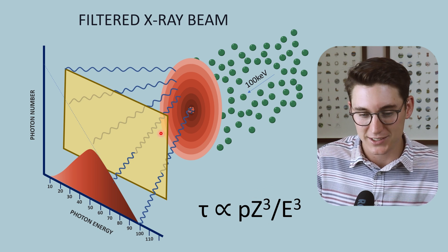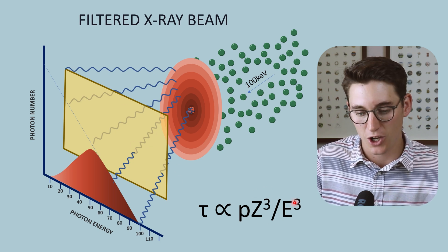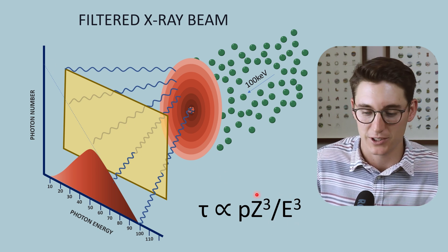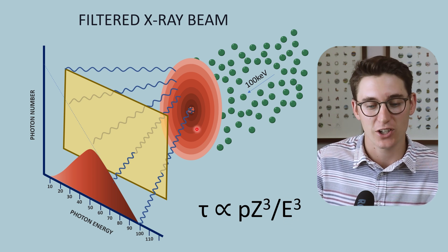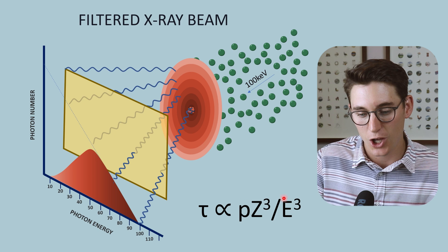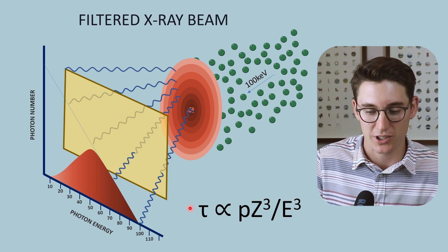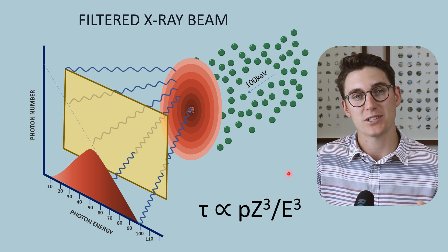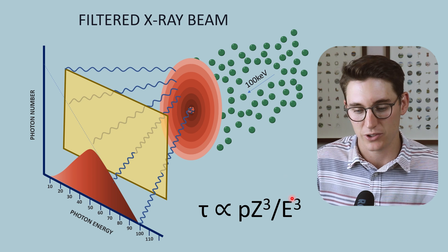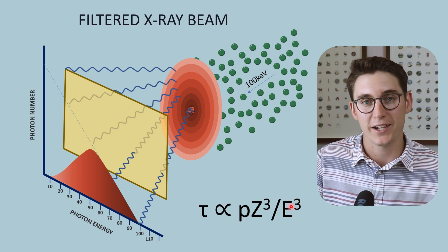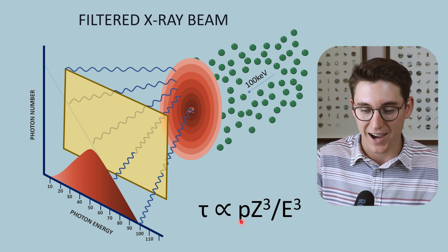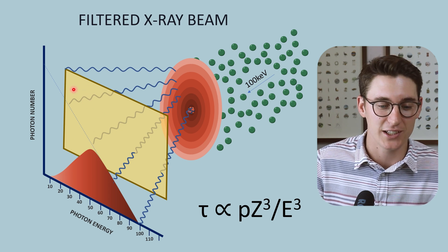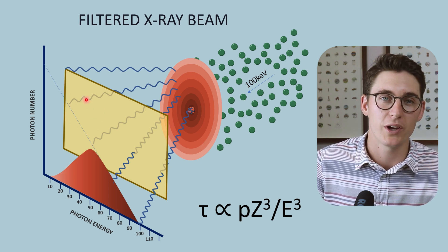For set filters, density and atomic number remain constant. What changes is the energy of the x-ray photon interacting with that filter. If we increase the x-ray photon energy, we decrease the likelihood of the photoelectric effect, because energy appears in the denominator — as energy increases, the denominator increases and likelihood decreases. So our low energy x-rays give a low denominator and a higher likelihood of the photoelectric effect, which is why filters preferentially remove lower energy x-rays.